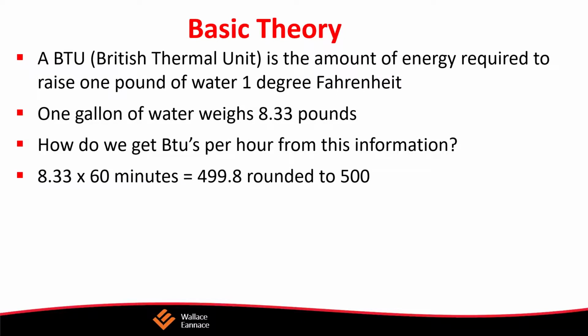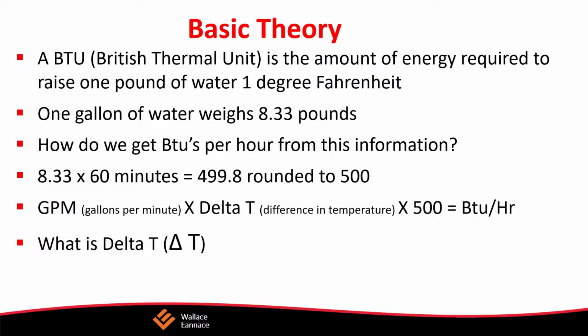So from that information, how do we get BTUs? Well, 8.33 times 60 minutes is about 499.8, which is rounded off to about 500. So if I have gallons per minute times a change in temperature times 500, that will give me BTUs per hour.